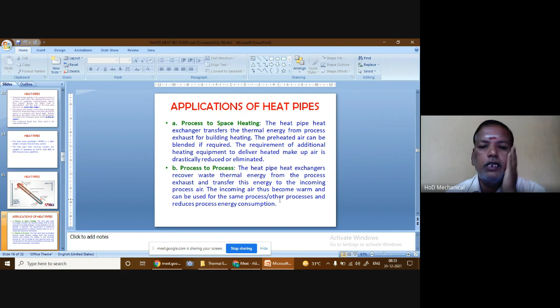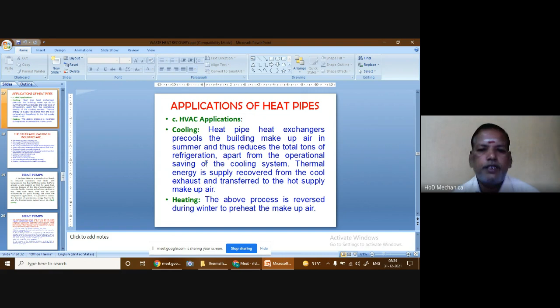One is the cooling application. Heat pipe heat exchangers pre-cool the building makeup air in summer, and this reduces the total tons of refrigeration, apart from the operational saving of the cooling system. Thermal energy is recovered from the cool exhaust and transferred to the hot supply makeup air. For heating, the above process is reversed during the winter to preheat the makeup air. As I told, in the hill stations we make use of heat pipes for space heating applications.